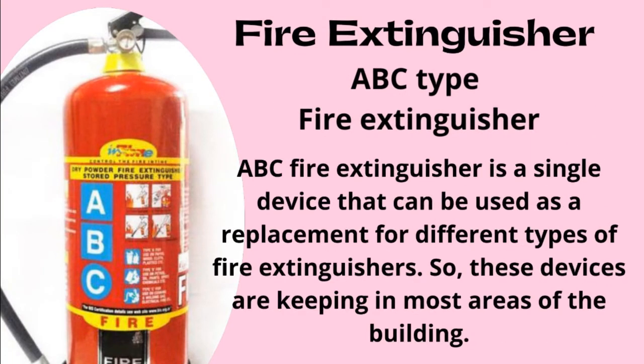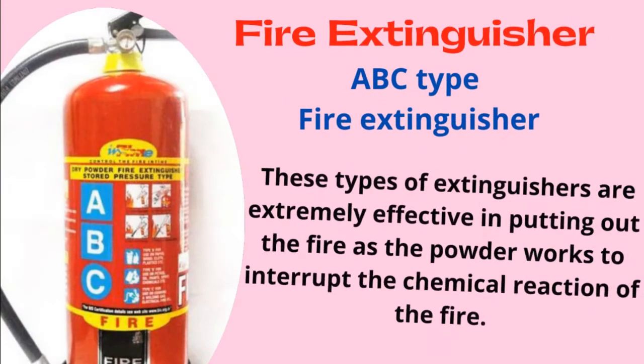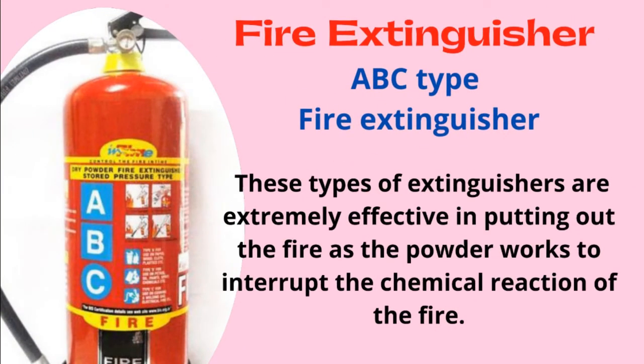ABC type fire extinguisher. An ABC fire extinguisher is a single device that can be used as a replacement for different types of fire extinguishers, so these devices are kept in most areas of a building. ABC fire extinguishers usually use a combination of mono ammonium phosphate and ammonium sulfate. It is often colloquially simplified as ABC dry chemical or multipurpose dry chemical. These types of extinguishers are extremely effective in putting out fires as the powder works to interrupt the chemical reaction of the fire.